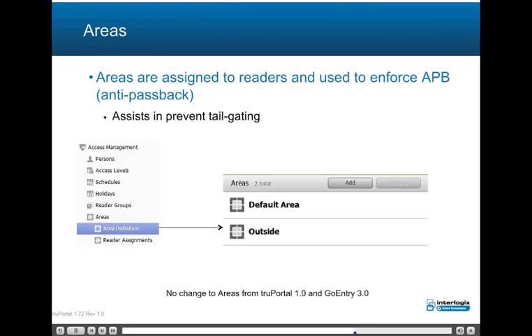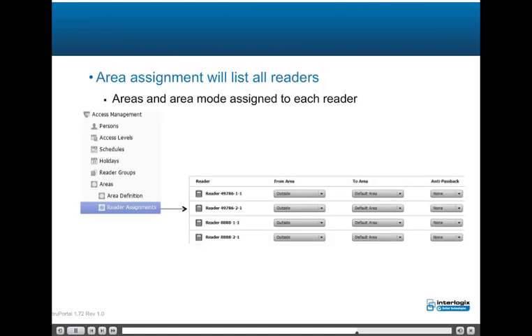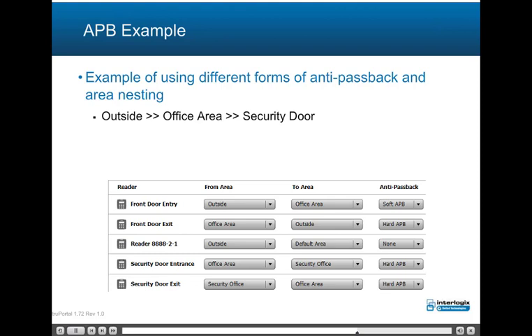Areas are assigned to readers and used to enforce APB (anti-passback) to assist and prevent tailgating. Areas are first configured by naming the area and setting anti-passback auto reset to never reset, or timed (10 minutes to 12 hours). The areas will be assigned to readers with settings for 'to area', 'from area', and anti-passback mode: none, soft, or hard. Area assignment will list all readers, and areas and area mode assigned to each reader, with an example of using different forms of anti-passback and area nesting such as an outside office area security door.